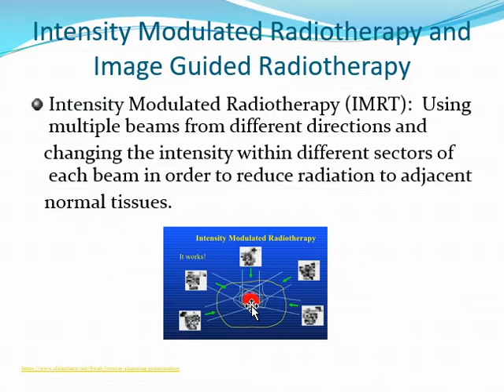So that's one way to deliver the dose more focally, but beyond that, the beam itself is very complex because there's leaves on the head of the machine which modulate the intensity. So this color map is basically showing the relative differences of high doses versus low doses. And you can see that you can have very complex dose distributions on each beam angle, and they can dynamically change. So it's the beam angles plus the intensity modulation that really helps you put the dose where you want it relatively.